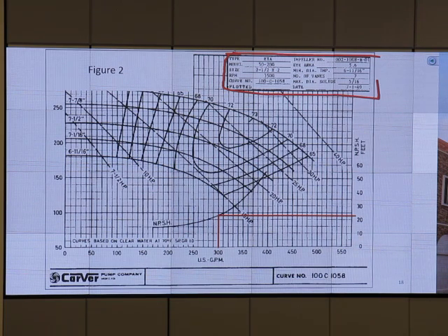We ran water flood pumps in the Middle East at 125,000 barrels a day injection. That's 3,700 gallons a minute. Everything is critical. So for what we're talking about here, and for a lot of smaller pumps like you use inside a battery or something like that, these pump curves will be good for general use, lower volumes, and so on. But if you really get up to bigger money, then you need to request certified curves on your pump. Pay more, right? Or how much more? You're going to pay more, but 10%. Yeah, you eventually have to pay more and get the test at your condition.